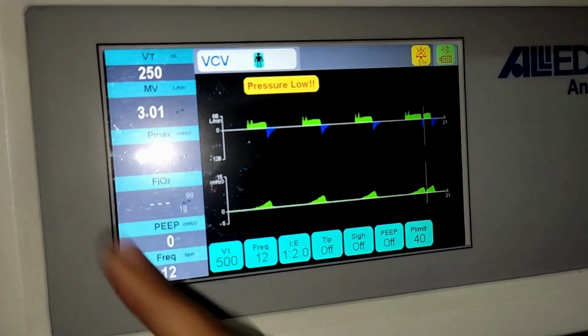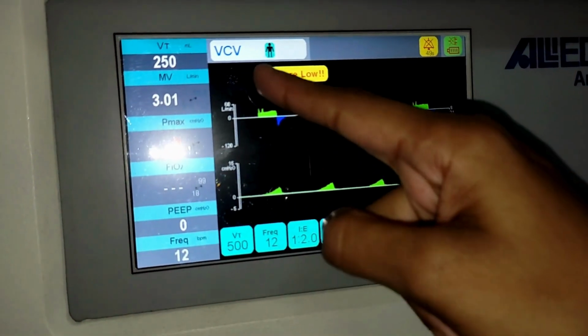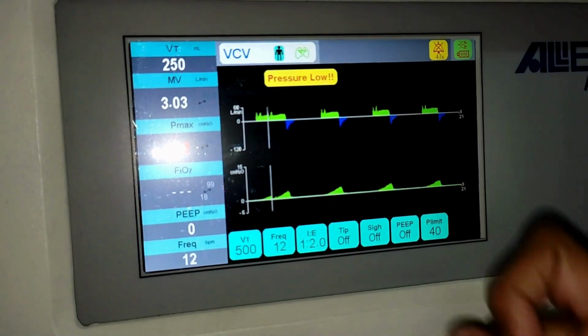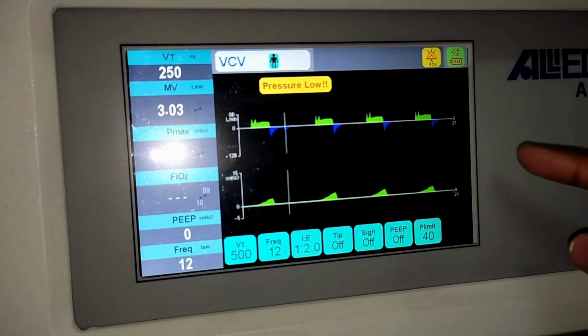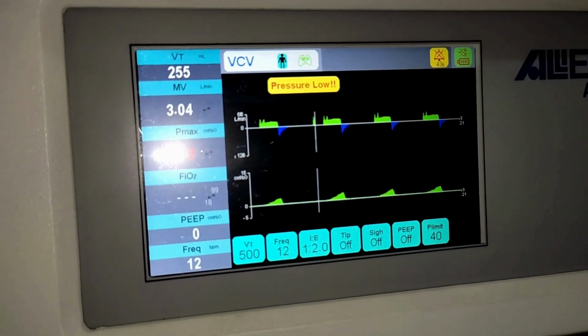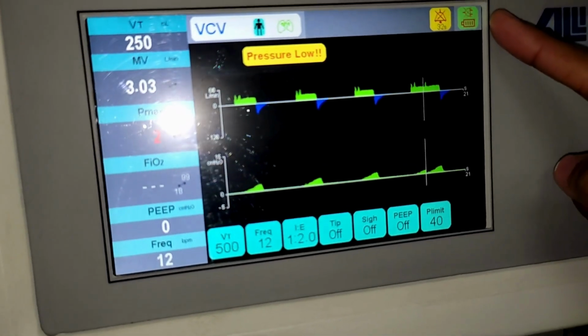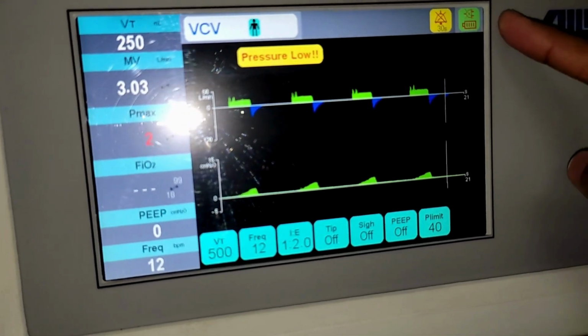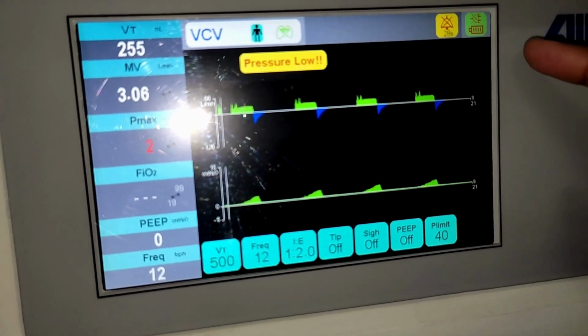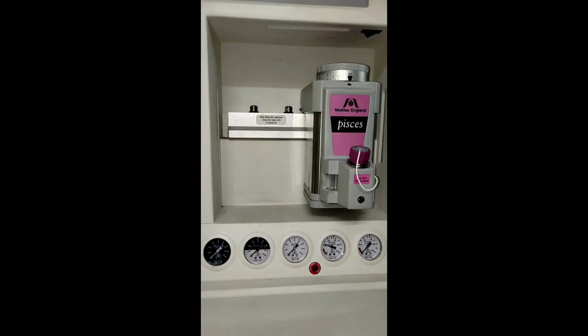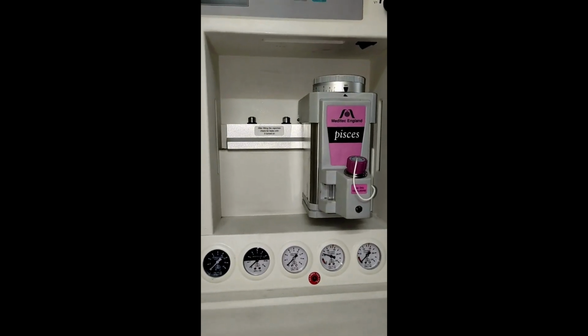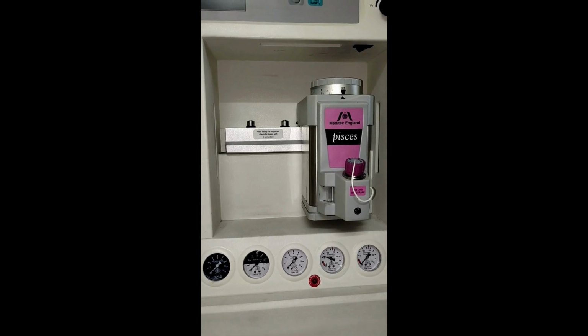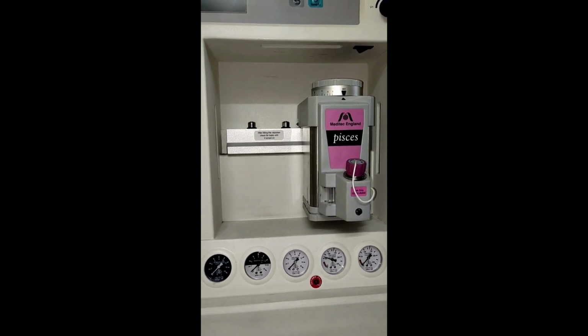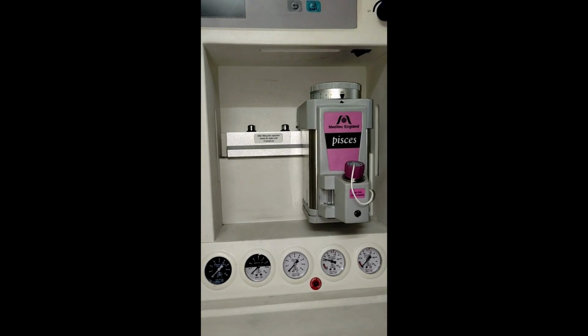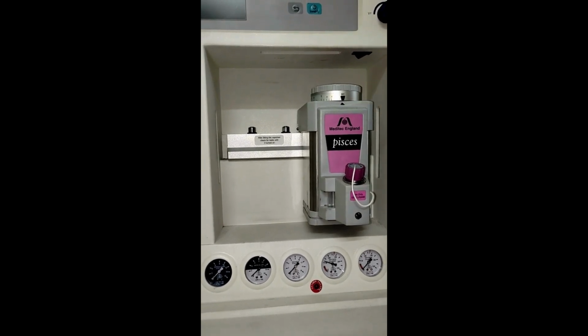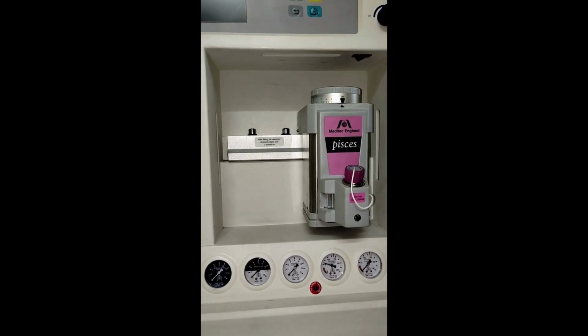These are the set parameters, these are the measured parameters. Here we can observe the mode of ventilation. These are the waveforms and loops. Here we can see the power status, whether it is running on battery or AC supply. Vaporizers are used to convert the liquid anesthetic to vapor for patient administration. Here they provided 2 slots for vaporizers.